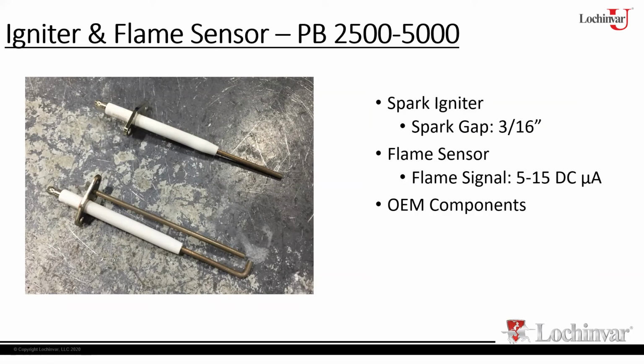Realistically, the only times you ever need to replace rods or igniters is if there's either physical damage to the rod itself, like it's burned off to where it's no longer sitting in the flame, or if there's physical damage to the porcelain insulator causing something to ground out. Otherwise, you clean the rods off, put them back in, you're good to go.